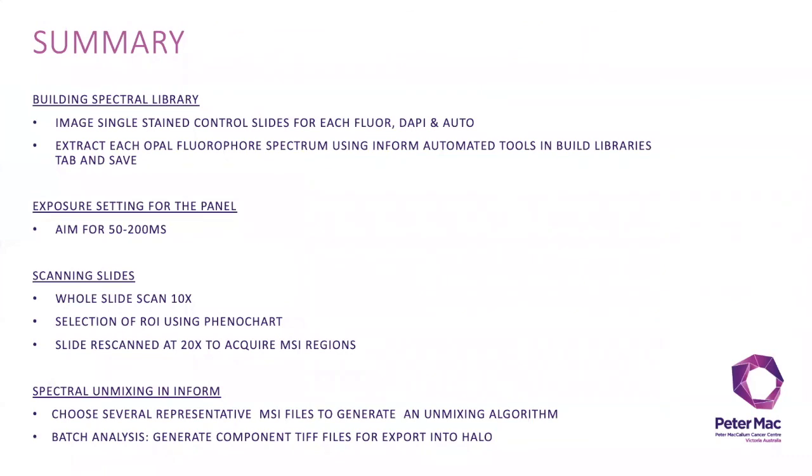So just to summarize the Vectra 3 imaging workflow. The first step is to image your single stain control library slides using the Vectra and then to build your spectral library using InForm. After setting your exposures for each slide the Vectra 3 imaging platform is used to scan the entire fluorescent slide at times ten magnification. The whole slide image is then loaded into PhenoChart for manual annotation of your regions of interest after which the slide is rescanned at high magnification to acquire your multispectral images. InForm software is then used to perform the spectral unmixing of your MSI files which are then batch analyzed to generate your component TIF files which can be exported into Halo for image analysis.